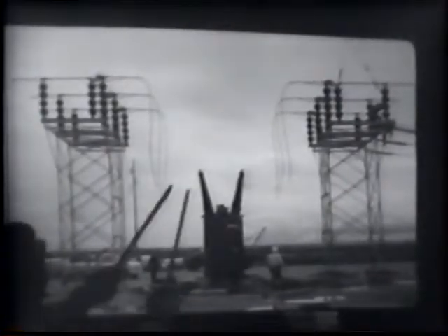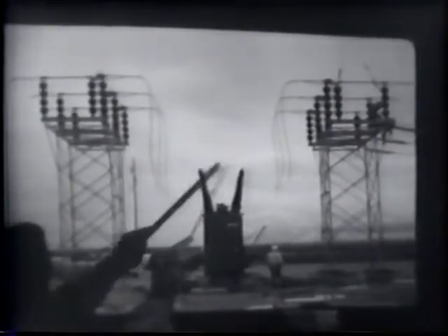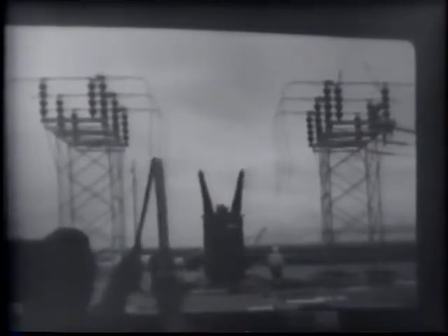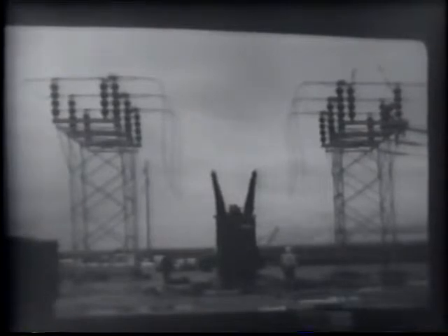This particular view here shows some of the factors as far as structure design. In this case, we have isolation from the breaker terminals to the steel structure on either side. We have a flexible copper conductor that will be attached to a bushing here that allows for expansion. It's also of sufficient capacity to carry the breaker rating. And as you can see in this location here, we have space that we can move the circuit breaker in and out. This little pad here is the pad for the operating mechanism, to allow easy access to the operating mechanism.